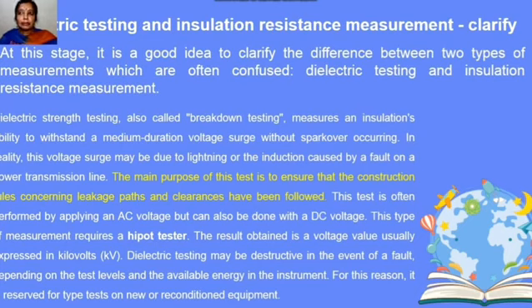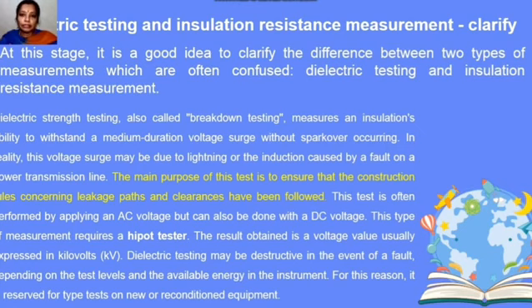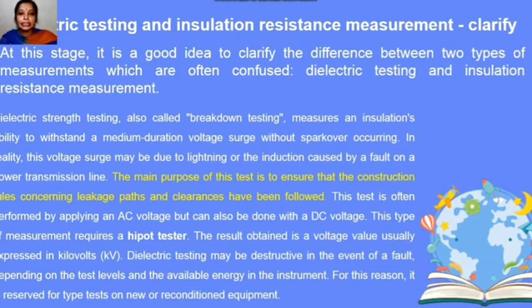Dielectric testing and insulation resistance are two terms often used, and it is important to clarify the difference. Dielectric stress testing, also known as breakdown testing, measures the insulation's ability to withstand medium-duration voltage stress without breakdown occurring. The voltage stress may be due to lightning, switching overvoltages, or other faults. This test ensures construction rules concerning leakage path and clearance are followed, and is performed by applying an AC voltage, sometimes DC voltage.